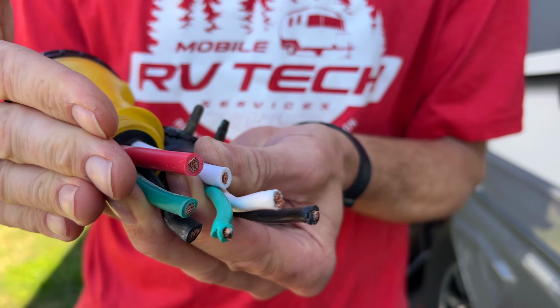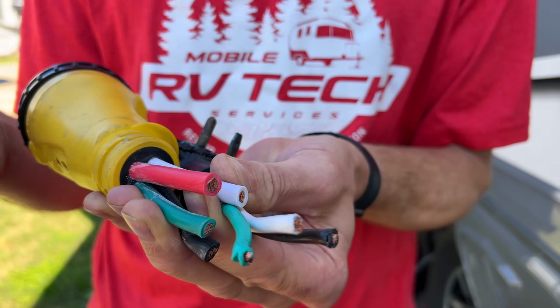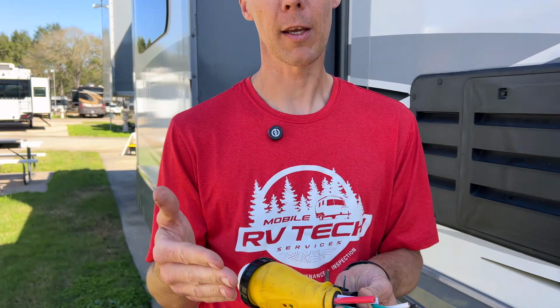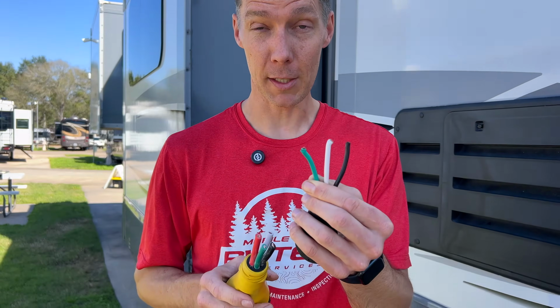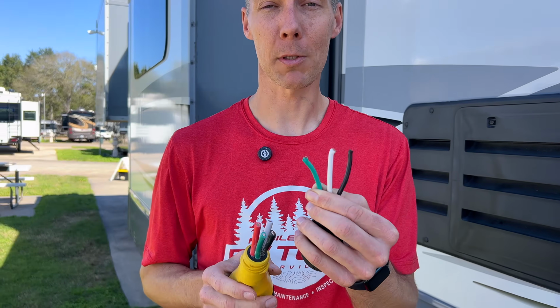Now, yes, there is a 30 amp breaker inside of your RV, which should protect your RV and limit it to 30 amps. But if you're getting more than 30 amps of power by using an adapter outside of your RV, that means your circuit breaker inside your RV at the breaker panel box is faulty, and now you have more than 30 amps flowing through a wire that's only rated for 30 amps. That is a fire hazard waiting to happen.